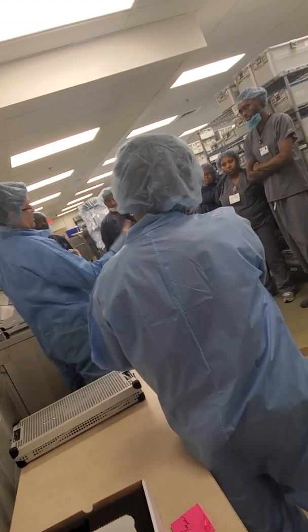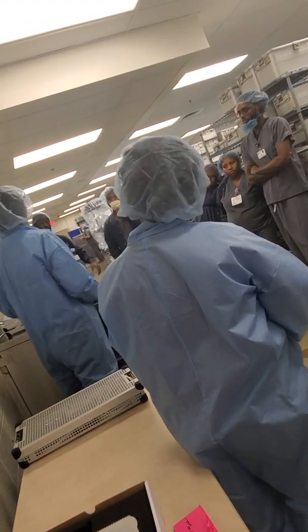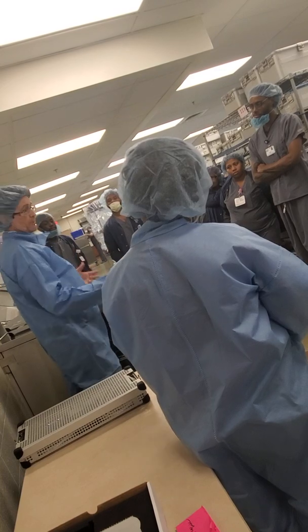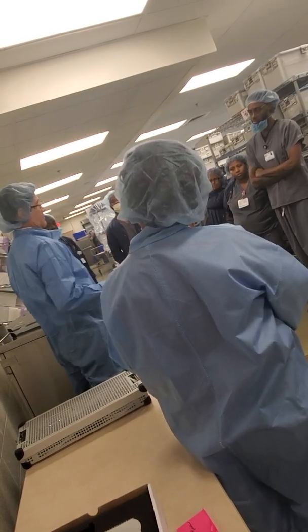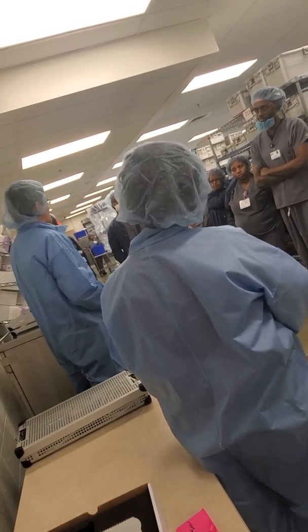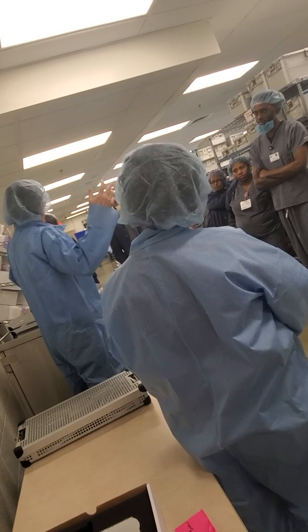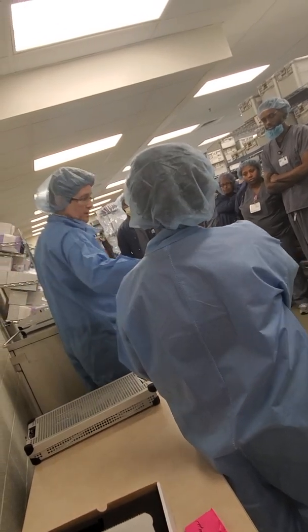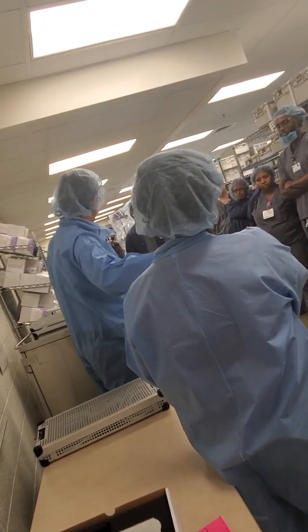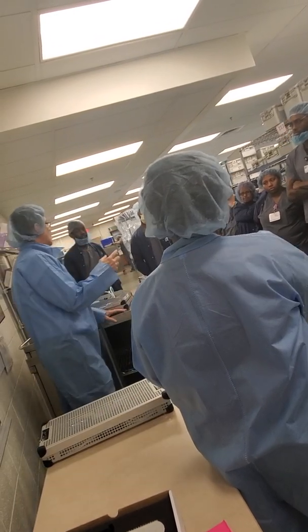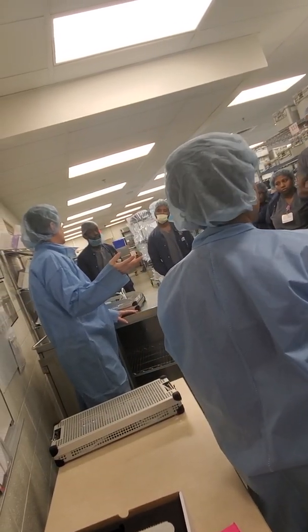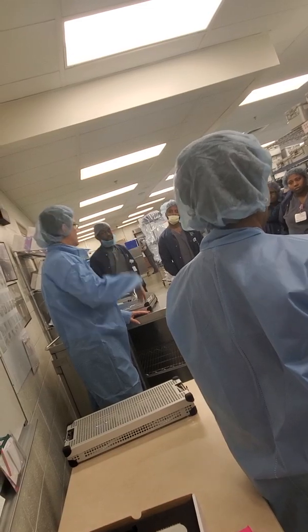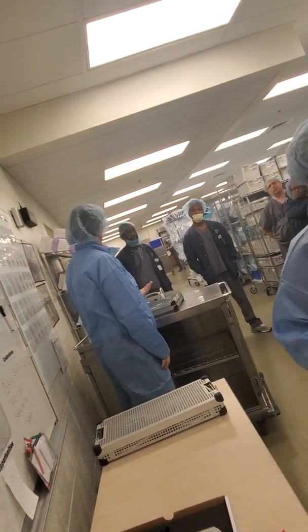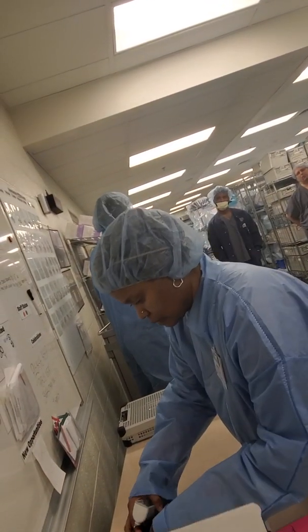I had a customer I was talking about. Well, let's go do it. So we took their probe, brand new leak tester. Well, I put it on, we pumped it up, looks good, put it in the water. Oh my God, there's bubbles coming out. What? Well, the bubbles were coming out of this piece right here in the cap. So it turns out it was just a faulty cap. So they replaced the cap, everything worked fine. See what I mean? Because my eyes like popped out. What? No, I see bubbles. Where?